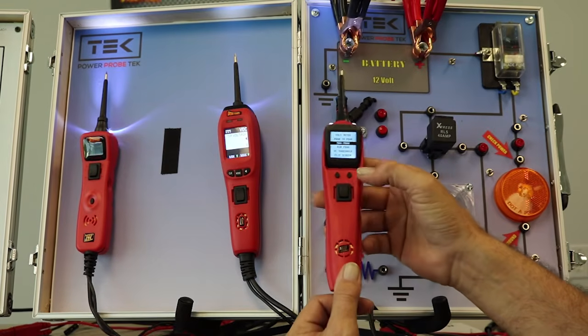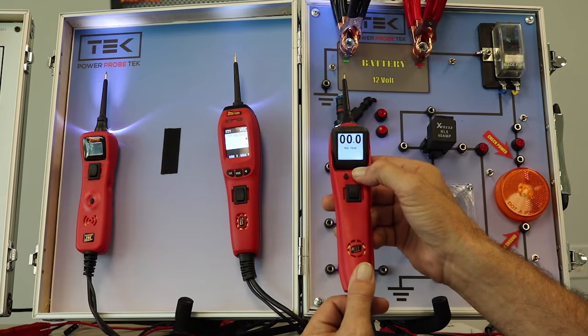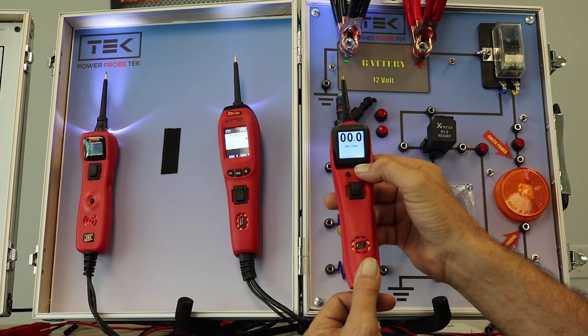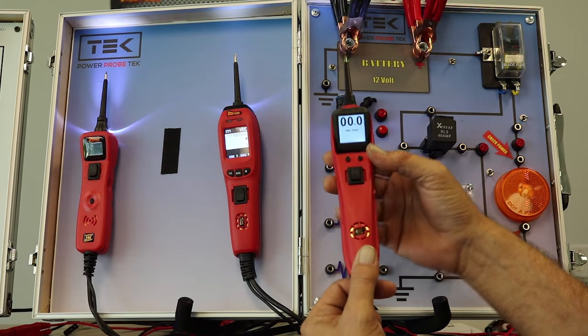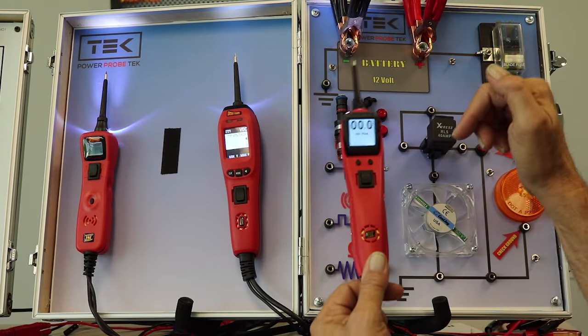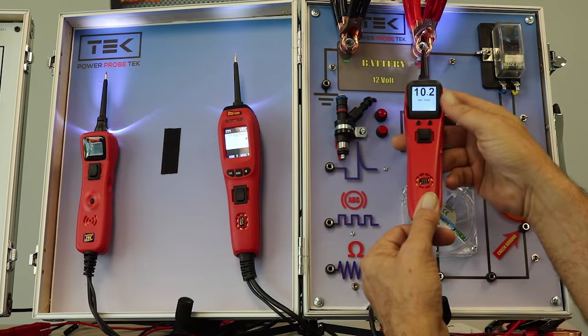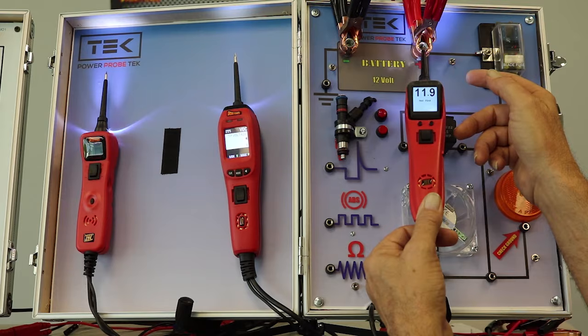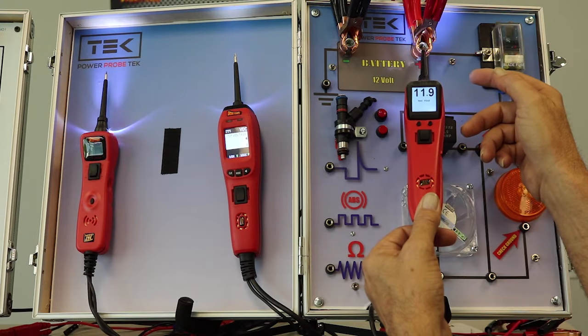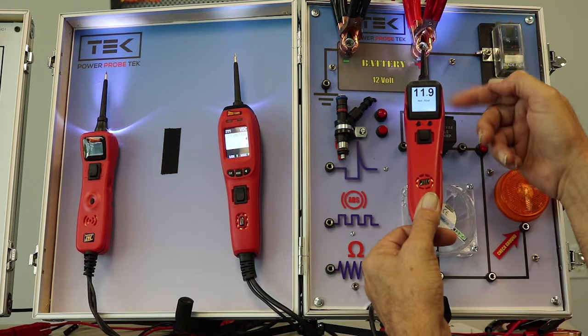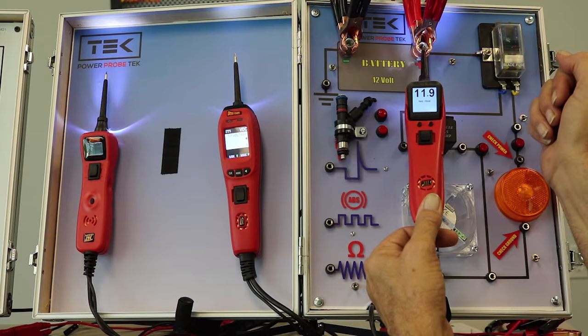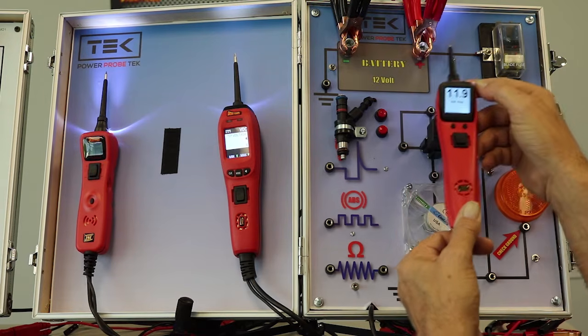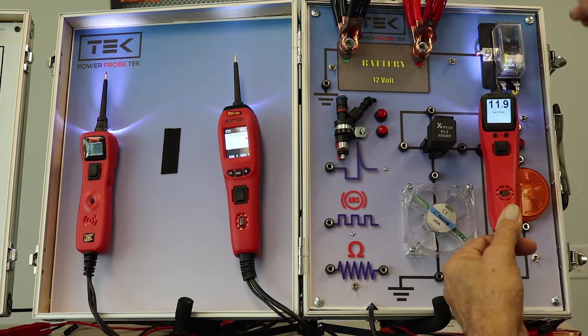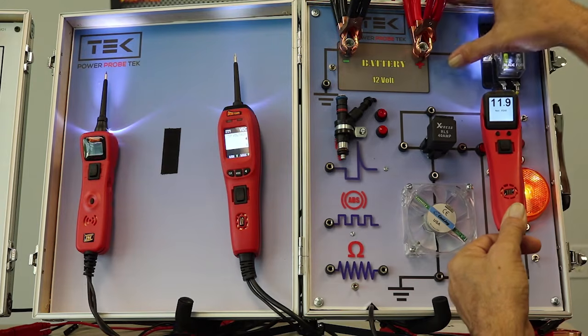The next mode down here is called max peak. You would use this while monitoring a circuit, looking for spikes in voltage. You connect it to the circuit, and from that point on it's going to show the highest voltage reading of that circuit. Let me connect to another spot and clear, and we'll try to get a lower reading.